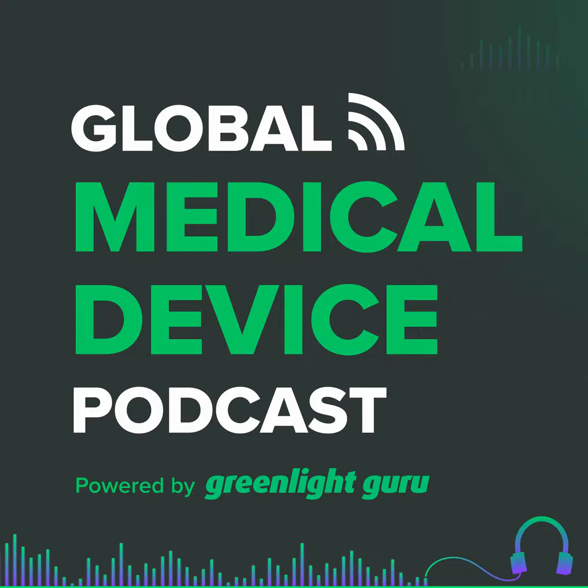So even in the case where you have a non-significant risk device, I almost always recommend taking it to the FDA first, usually in the form of a pre-sub. Want to guess as to why I recommend doing that, Etienne, even though it's not required? Why would a company take an NSR device to the FDA, usually as part of a pre-sub, when it's not required? Well, personally, I would not want them to upclass that to a significant risk and then potentially invalidate whatever clinical investigation I'm performing. Very good.